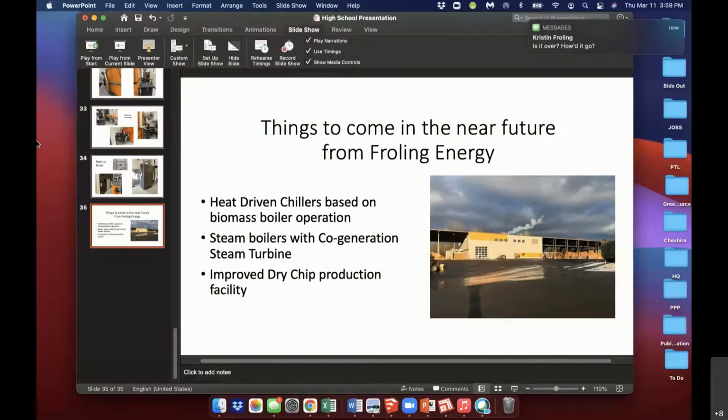Okay, we've got Bill is asking, on average, how many ignition cycles do you see a day? Is the boiler modulated so it can reduce the output based on load to reduce ignition cycles? Yeah, on these two boilers, the smaller boiler at Campton, I will tell you, goes on about 3 times a day. That's about it. It goes up, it goes down, and it goes into a little bit of a maintenance mode as well for, I think, maybe 20 minutes or so. So it has the ability to keep a flame for a short amount of time. But it really only uses the igniter at max 3 times a day, even up until yesterday. So it turns off. When it goes on, it's always on for several hours.